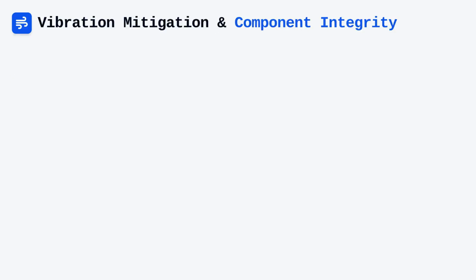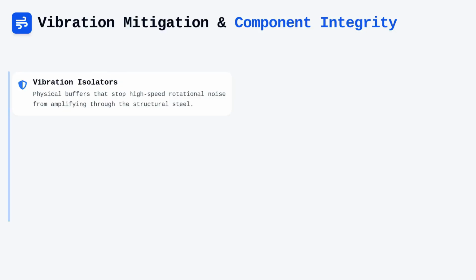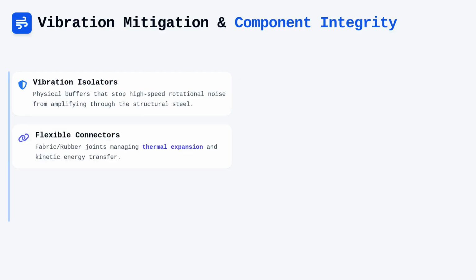To mitigate the transfer of mechanical noise and kinetic energy, manufacturers integrate vibration isolators and flexible connectors between the blower assembly and the ductwork. These components act as physical buffers, preventing the structural steel of the AHU from amplifying the vibrations generated by the high-speed rotational parts. Flexible connectors, typically made of high-strength fabric or specialized rubber, also allow for thermal expansion of the equipment without placing stress on the connected duct sections.